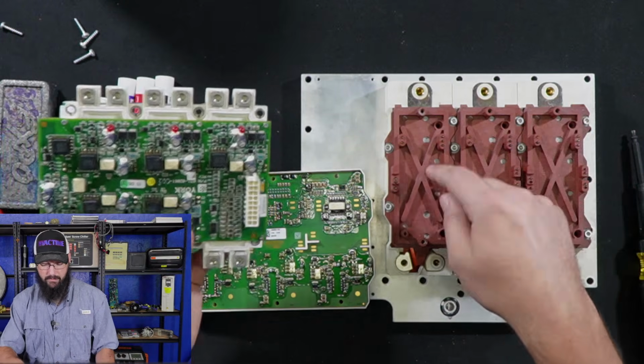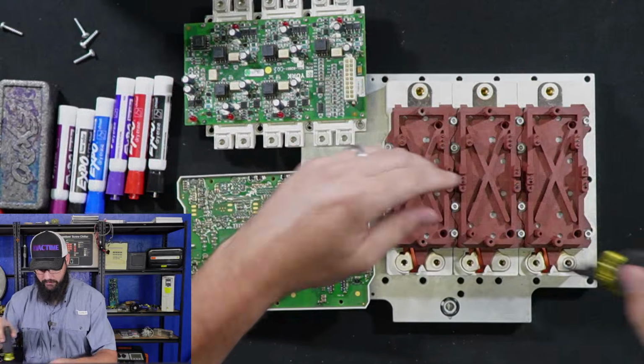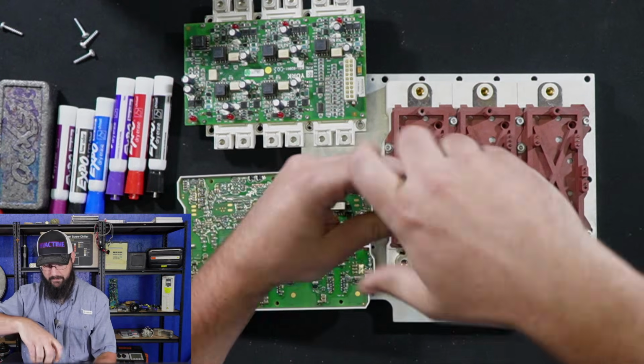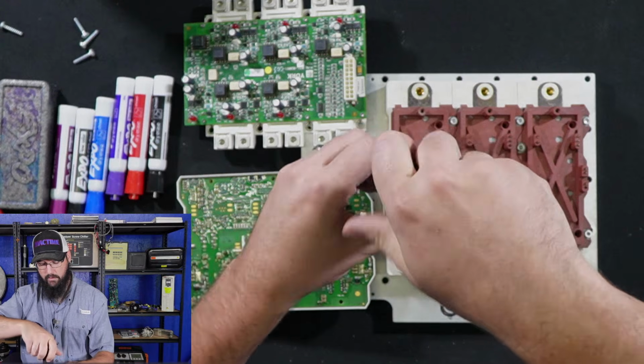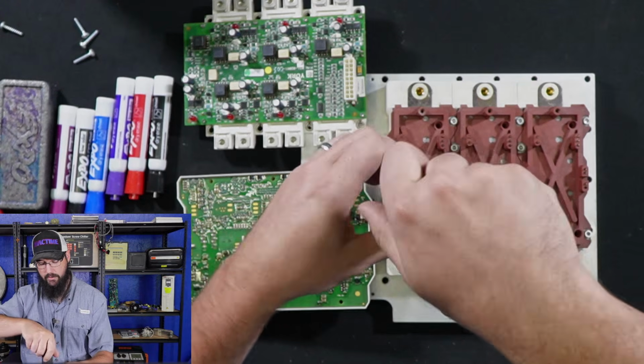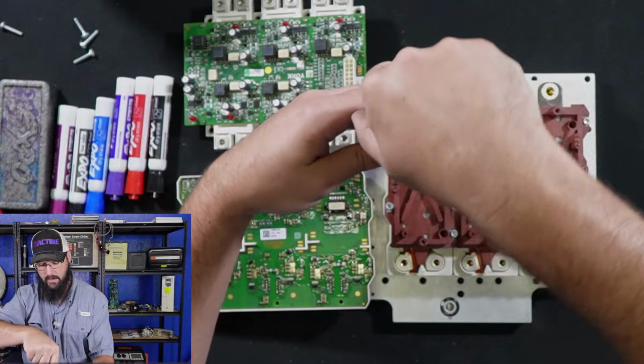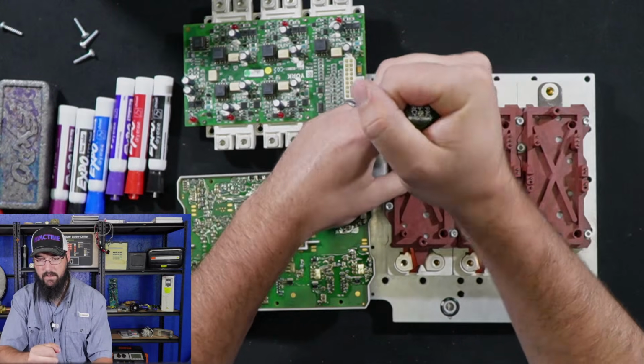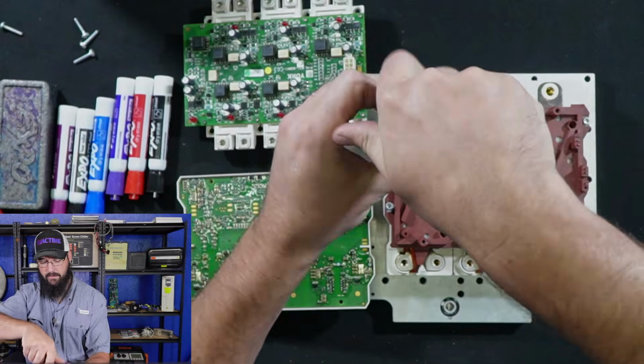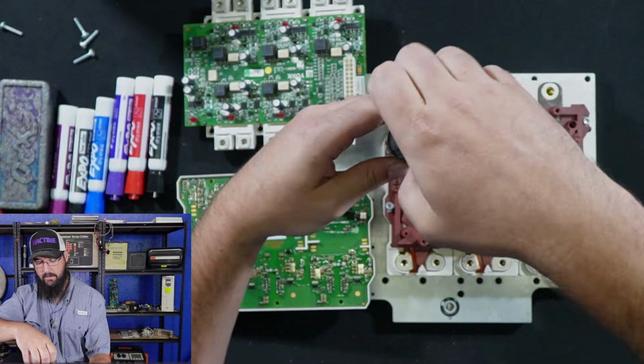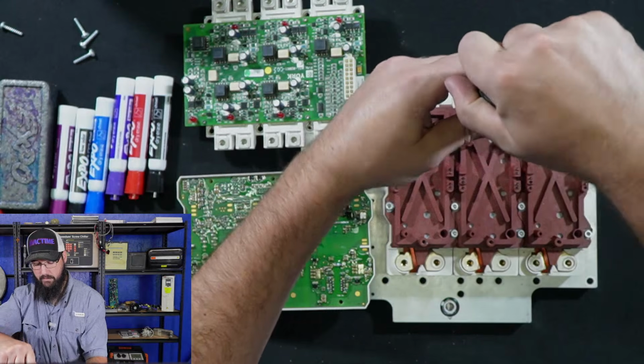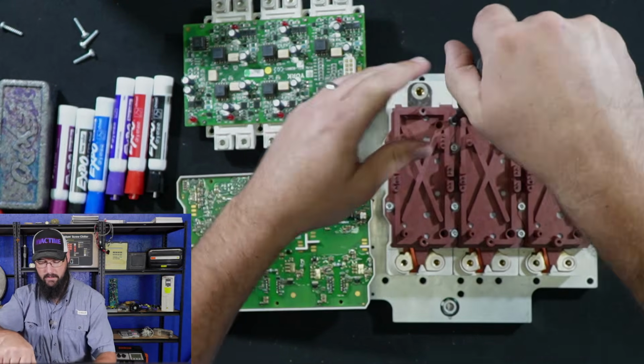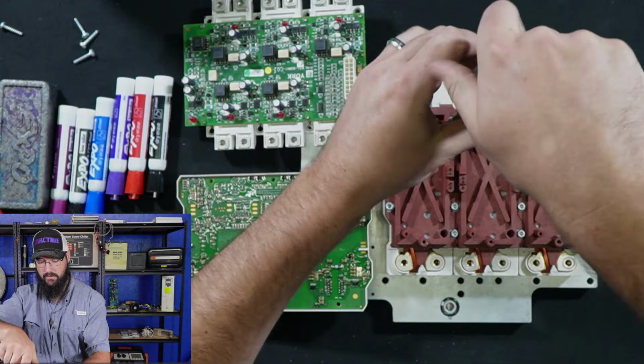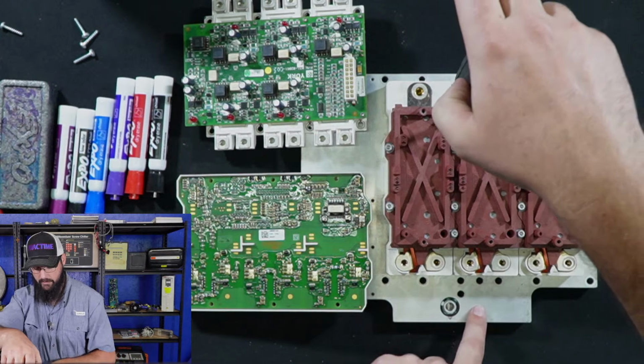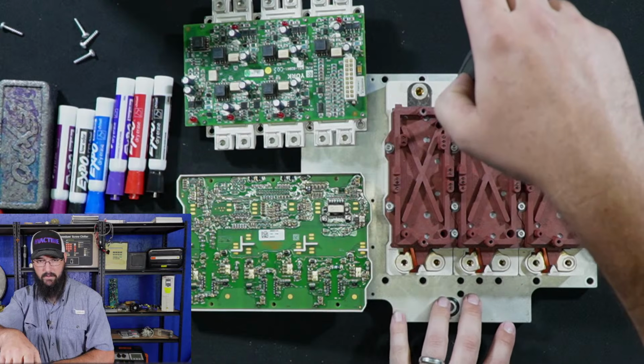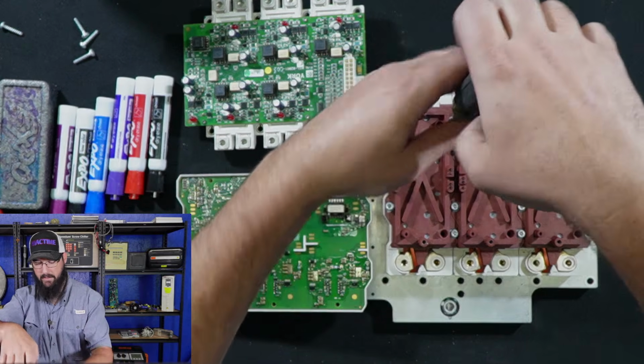And we could even strip this apart further. We can see one of those. We'll just do one of them. Again, this is one of the reasons why I encourage going to trainings where they allow you to do this kind of stuff, because this is not something you would do in the field. You're not going to strip this down in the field. If this module was to fail, you would just replace this whole plate assembly, because this is the cooling plate that it's sitting on. The DC converter would go here. Your SCR plate assembly would attach over here and kind of come up and out.